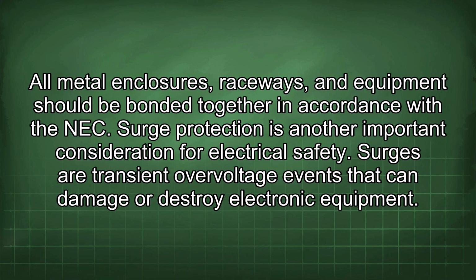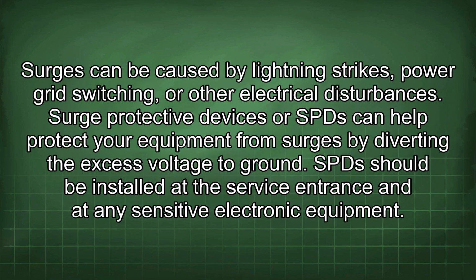Surge protection is another important consideration for electrical safety. Surges are transient overvoltage events that can damage or destroy electronic equipment. Surges can be caused by lightning strikes, power grid switching, or other electrical disturbances. Surge protective devices, or SPD, can help protect your equipment from surges by diverting the excess voltage to ground. SPD should be installed at the service entrance and at any sensitive electronic equipment.